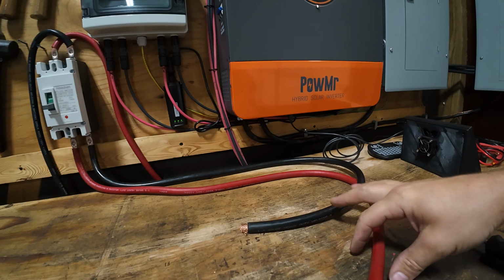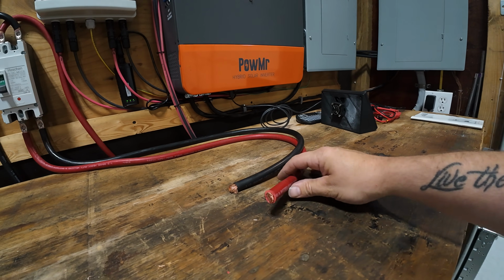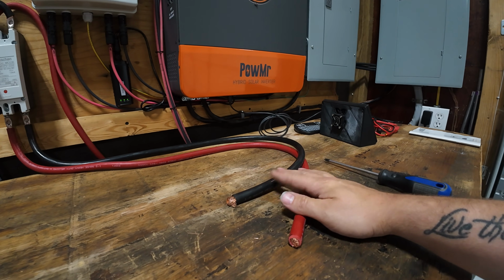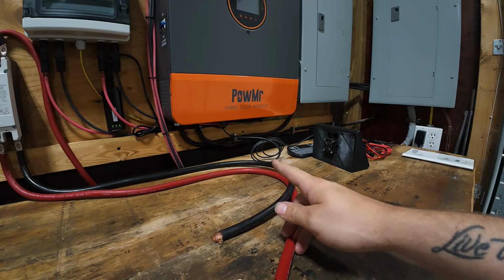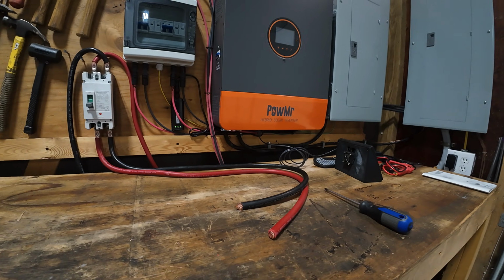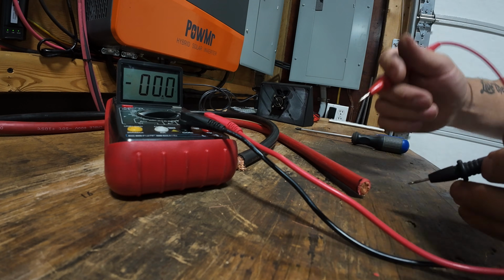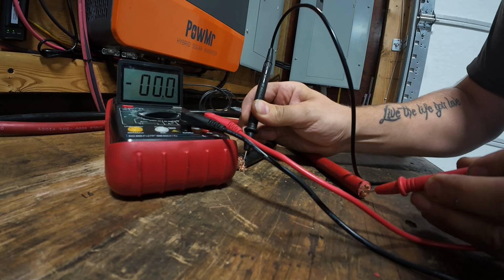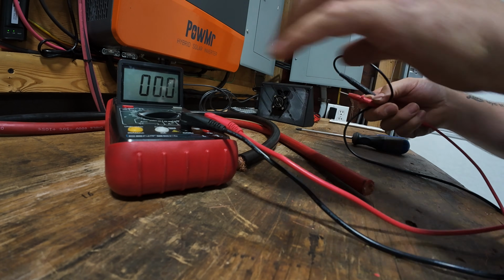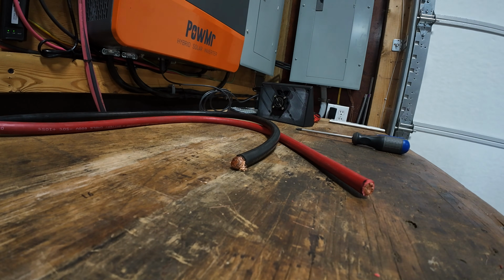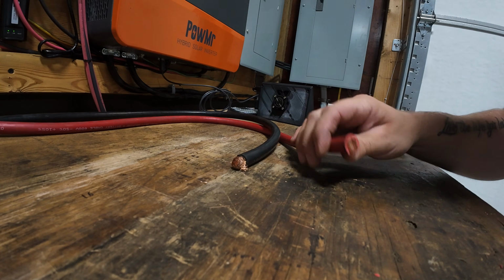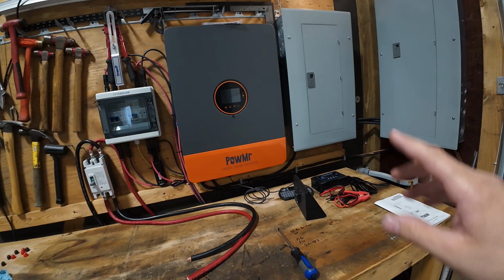Before we do that, I want to double check that we have no voltage on the ends of these cables, because you definitely don't want voltage on them when you hook them up to your inverter - it can blow your inverter up. Let's check that real quick. Okay, we've got this on DC volts, and we've got nothing, so that's good. It's always good to double check, just in case this was a bad breaker or something out of the box - you never know. So now we're going to shut down the inverter and turn off power to everything.